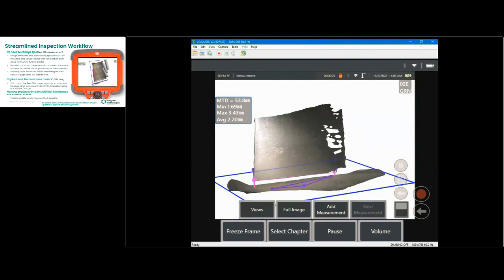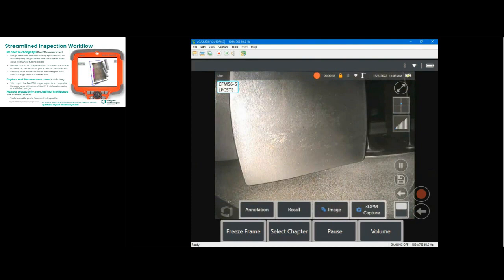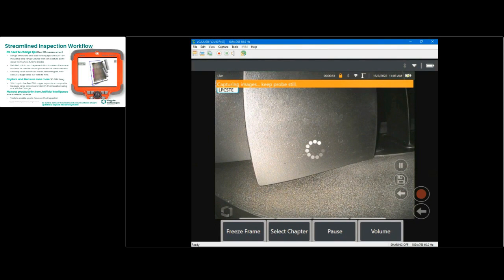It's able to recognize the tip of the blade and the shroud and basically be able to determine that distance across the chord of the blade and present all that information at maximum, minimum, and average size. So quickly just show you another image. Because auto repeat was pressed, you don't have to press blade tip clearance. So one button press and it's going to capture a blade tip clearance measurement, and within a few seconds there you have it again for blade number two.